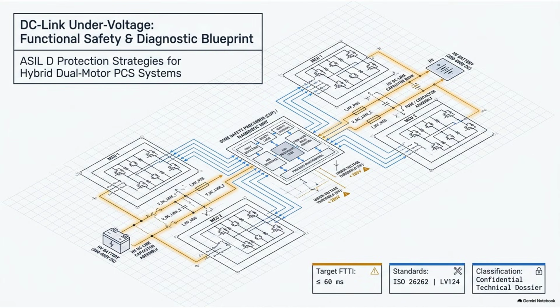We need to do a root cause analysis. The documents outline four distinct physical dimensions, four completely different ways this DC link under voltage fault can trigger. They really cover all the bases. I want to look at the first one, categorized as a high voltage disconnection. If I'm tracking the terminology, this involves the main battery suddenly cutting out.